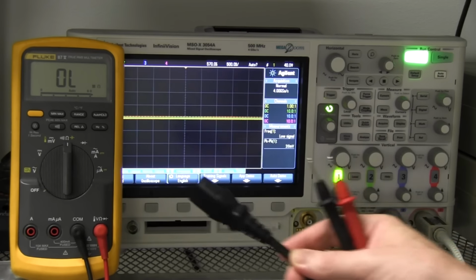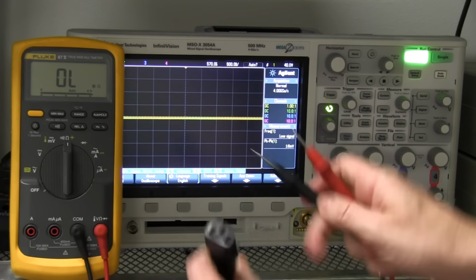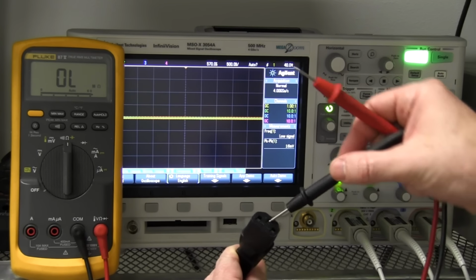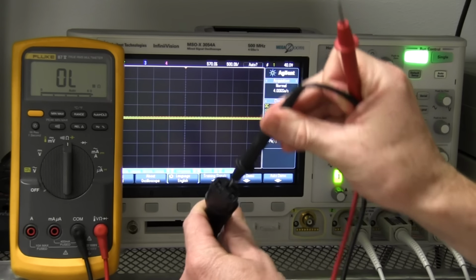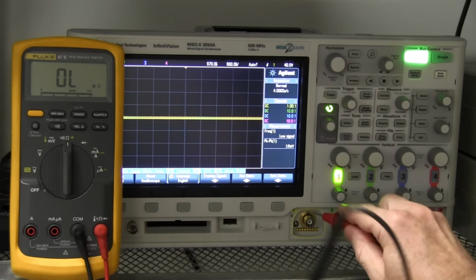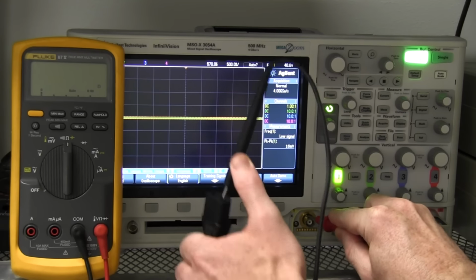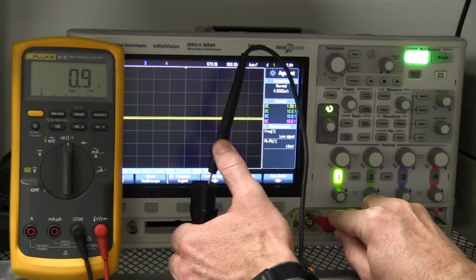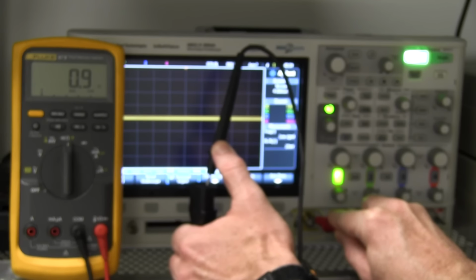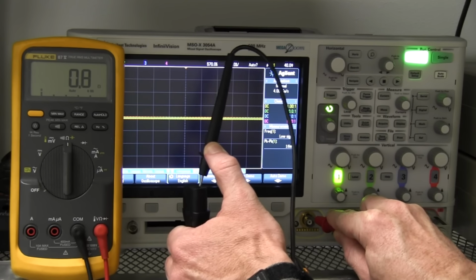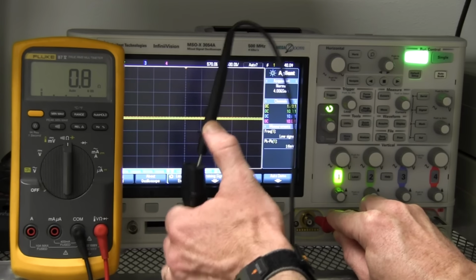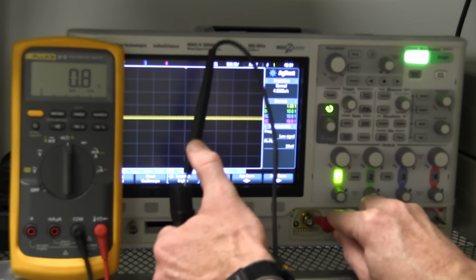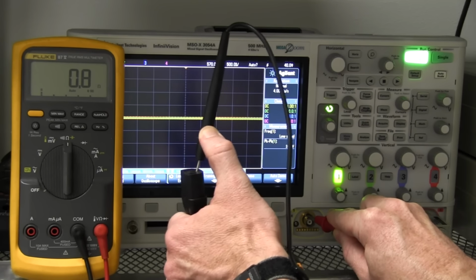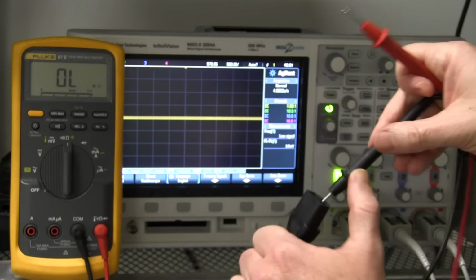So I've got my multimeter here set to ohms. Let's make sure we probe the right thing. I'm going to probe earth, the center earth pin there, and I'm going to probe the BNC. And there it is, 0.9 ohms. It's effectively a dead short. There's some DC resistance in there, but it's a very low resistance path. Effectively, well, it is a dead short through to mains earth, and that can be problematic, as I'll explain.